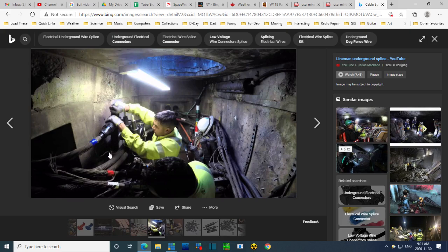So one of the things that can happen in a manhole like this is if you have a cable failure and the failure is not snuffed out fast enough, in 5, 6, 7 cycles, it will set other things on fire. And I'm not talking about a small amount of heat here. You can make a huge amount of toast in a really quick moment with a fault on one of these cables. I have seen, I won't go into the stories of what I've seen right now, but believe me, it's also very explosive. When these things short out, they flash heat the air in here. This becomes a cannon. It blasts the manhole lid off the top, and it can blast it up 20, 30 feet in the air.